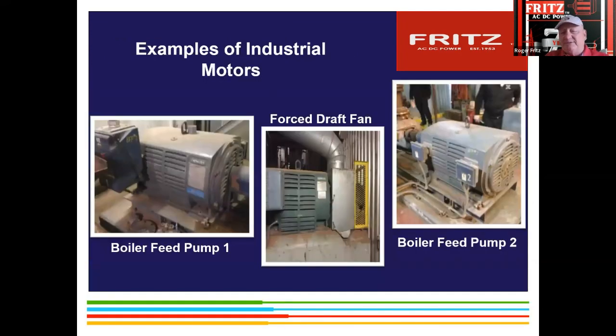These are some examples. These were medium voltage motors put in a power plant, about 750 horsepower. We put drives on the draft fans in the middle there, and on both the boiler feed pump 1 and pump 2, which feed the boiler water into the boilers so that they could control that. There was a 10% service factor that they had to build in, that they could never go over.